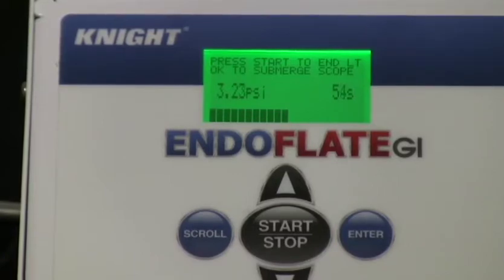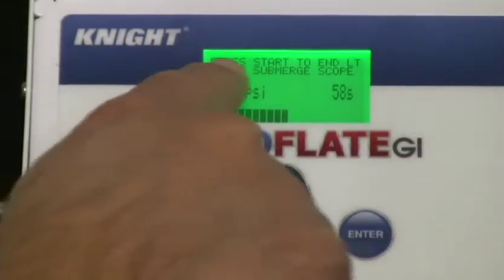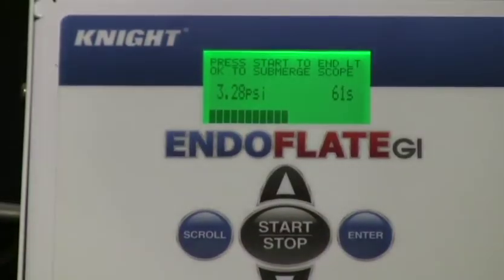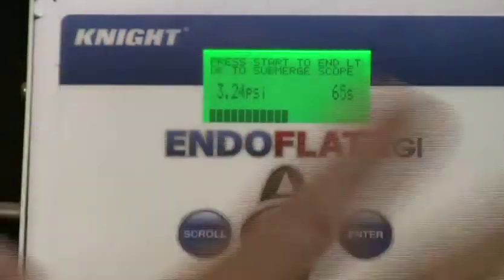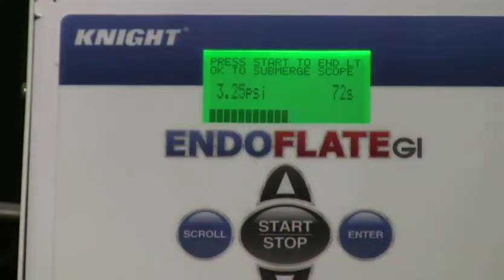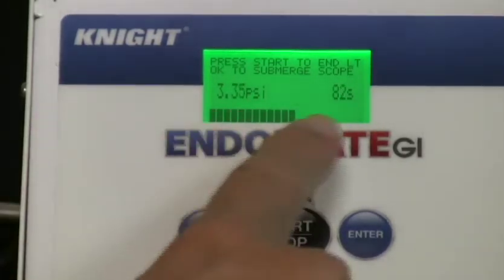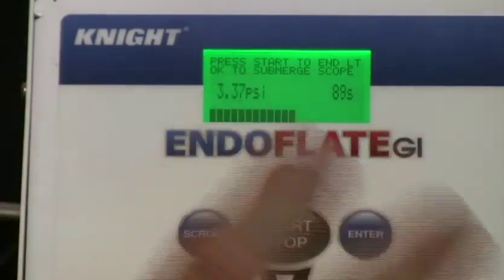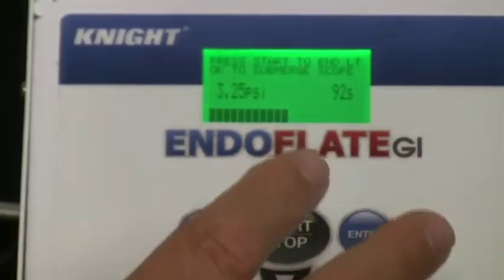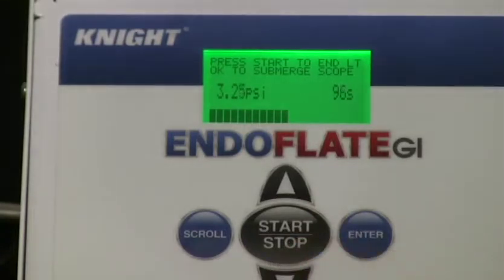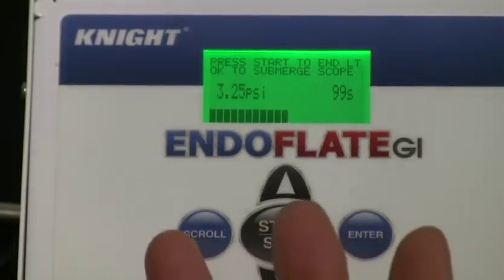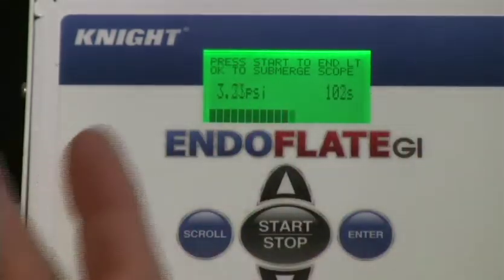Okay, so at this point we're going to remove the OK to submerge message here, just because we don't want to be the device that determines whether or not it's okay to submerge. If the number for PSI or millimeters of mercury or bars is drifting, then we'll show you how that looks when we're going in and out of the quiescent stable state. When we're in the green, that means that our air pump is fully inflated and holding stable. If it changes from green to blue, that means that the air pump is charging. If it changes to red and gives you a low pressure alert, that means that we're not able to fully pressurize the scope and there's a significant leak.